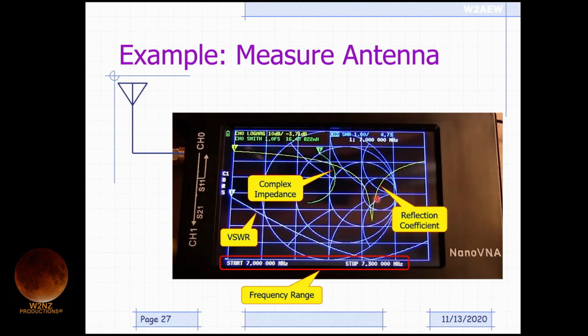So this is the reflection coefficient. Again, reflection coefficient and SWR are mathematically related to each other, so they're both going to give you the dip at the same point. It's often easier to see the location of that dip on a log magnitude reflection coefficient plot as opposed to SWR. It's very easy to see where that point is. It's a little bit shallower on the SWR plot. And we can tell that it is a reflection coefficient because it's on channel 0 and looking at log mag.